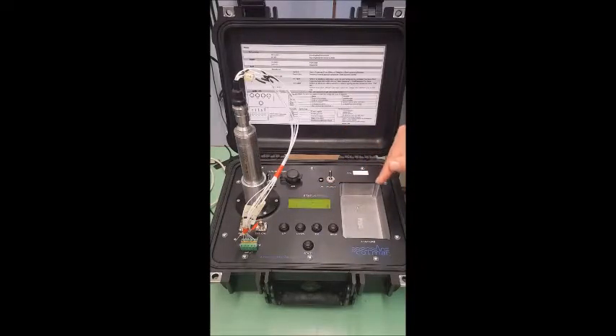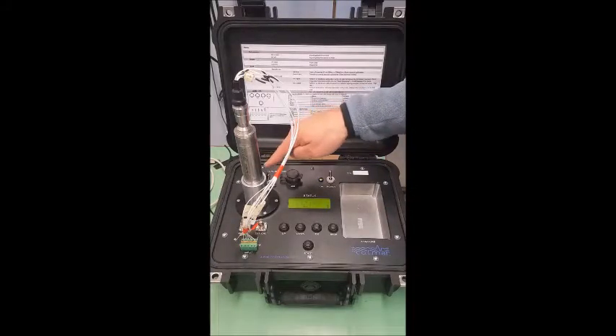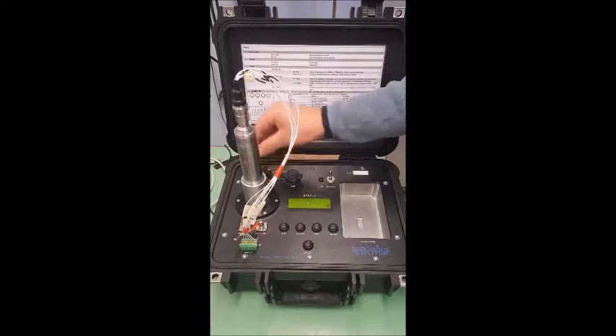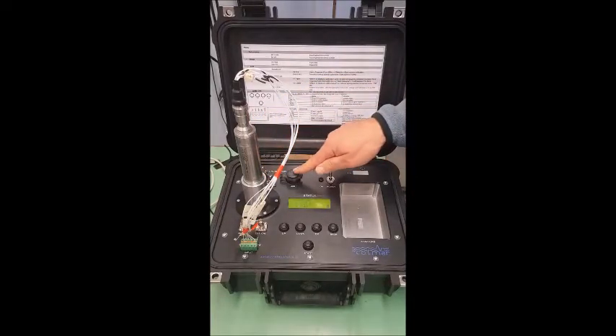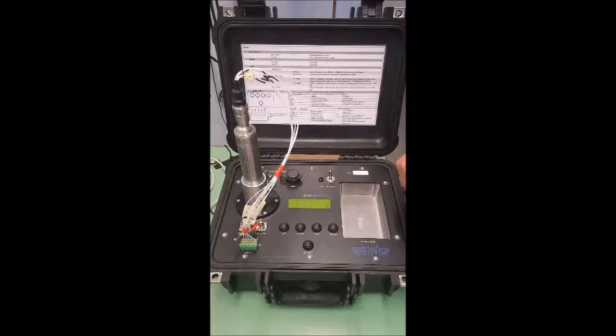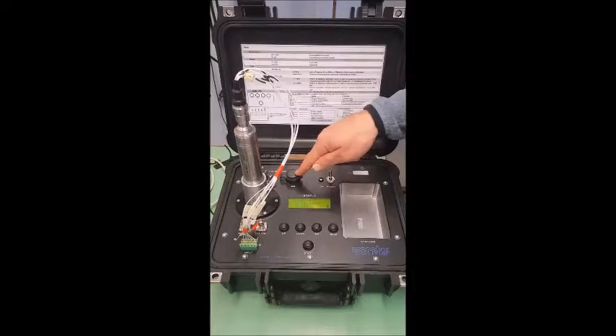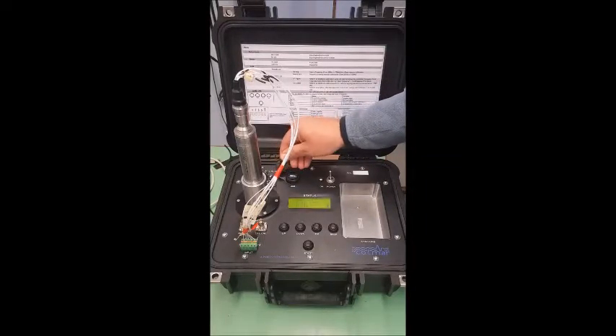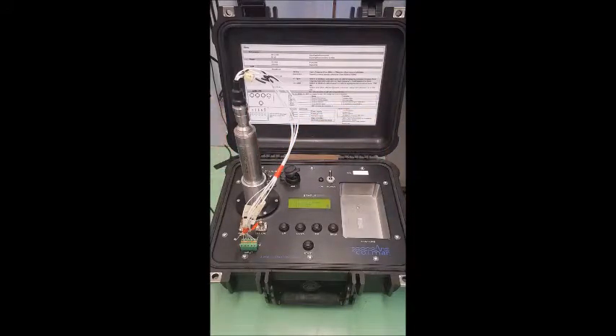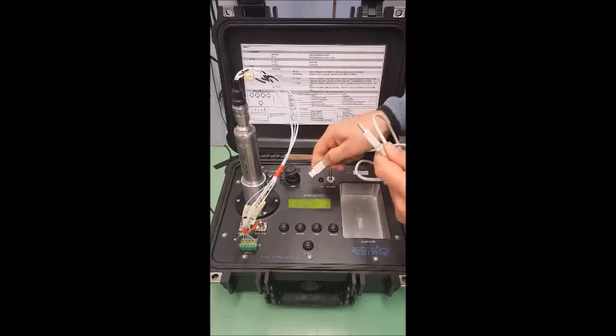The device is battery operated. This is needed in order to reduce the electrical interference from the mains. So when the batteries are depleted, it is possible to charge them, obviously, via this charge port that is on the device. The device also has a USB port. This port enables the user to download the data that is collected during the calibration. The data is presented in the form of a comma-separated values file, and this file is accessible as a USB storage device once the PC is connected via a USB cable, like this one, to a PC.